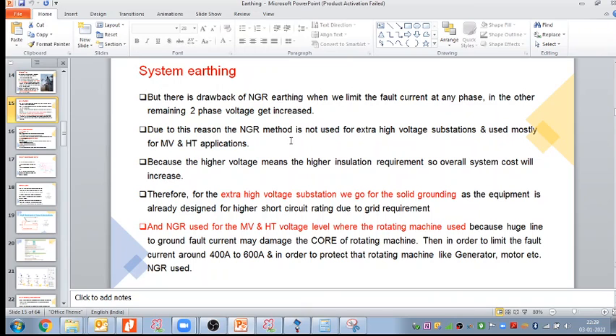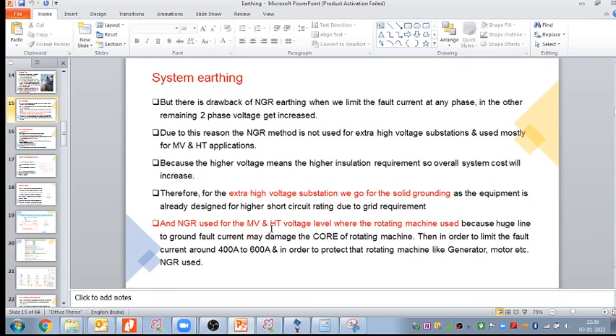Due to this reason, the NGR method is not used for extra high voltage substations and is used only for medium voltage and high tension applications. Now again, here is one sub clause, I'll come to that topic later on. Because higher voltage means higher insulation requirement, so overall system cost will increase. Therefore, for extra high voltage substations, we go for solid grounding, as the equipment is already designed for the higher short circuit rating due to the grid requirement, and NGR use.